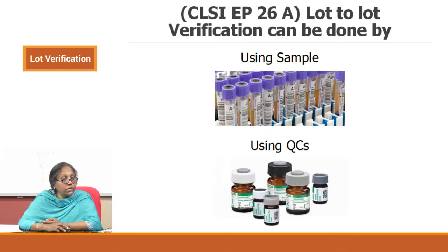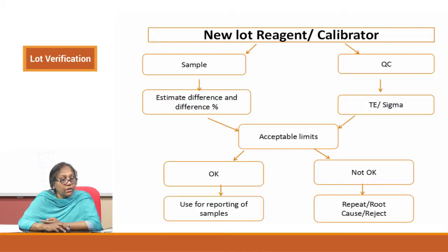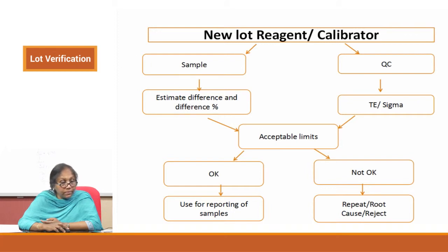We will talk about both these processes because CLSI has explained this in EP26A: lot-to-lot verification can be done using samples or using quality controls. For the sample method, after you run the test you estimate the difference or percentage difference between the runs and judge acceptability. If acceptable, you can use it for reporting. If not, you have to repeat and find the root cause, or if it is not working at all, you reject that lot.